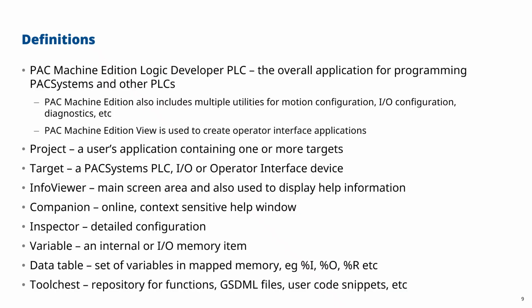Now, variables can be symbolic, in which case they stand alone, but we've also got mapped memory, such as %I for inputs, %O for outputs, %R for registers, and so on. In these cases, these are data tables consisting of multiple instances of that mapped memory. So that's where the data tables come in, and we can map variables to the data table or have them individually as symbolic addresses.